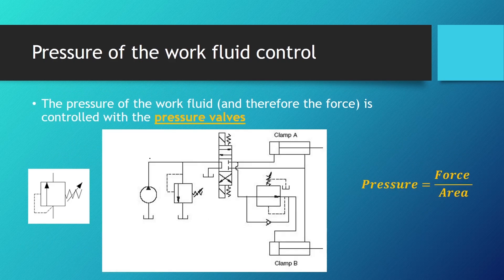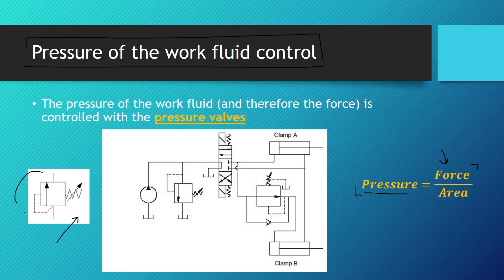What about the pressure of the work fluid? Pressure is equal to force divided by area, so by changing the pressure, we directly change the force. The pressure of the work fluid, and therefore the force, is controlled with pressure valves. Here we can see a pressure relief valve, which limits the pressure to a certain amount. When the system reaches that pressure, it opens up, releasing the excess fluid to the tank. In this pressure relief valve system, the force of the hydraulic cylinder extension is limited.